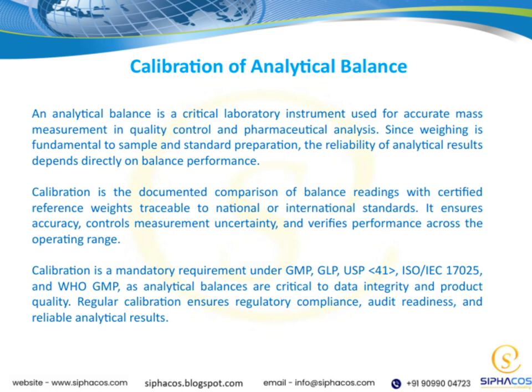It's important to remember that calibration isn't just a good practice. It's a mandatory requirement under regulations like GMP, GLP, USP, ISO IEC 17025, and WHO GMP. These standards recognize how critical analytical balances are for maintaining data integrity and product quality. Regular calibration isn't just about compliance. It's also about ensuring that our results are trustworthy. It keeps us audit-ready and guarantees that our measurements remain reliable over time.